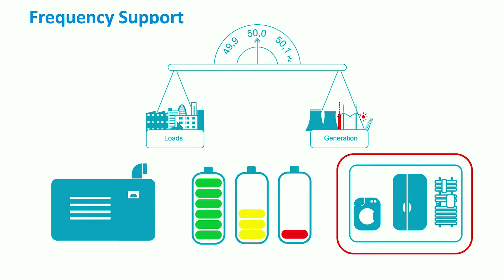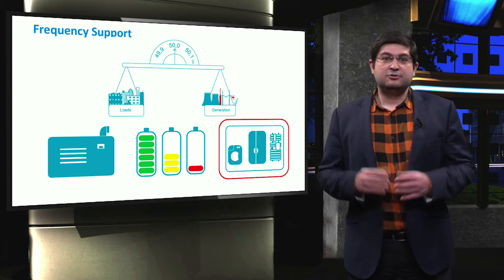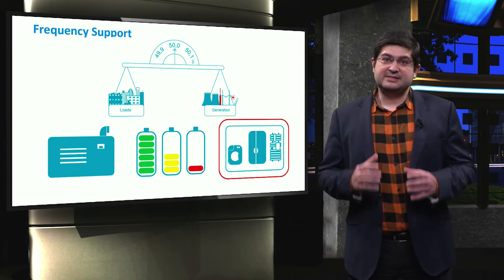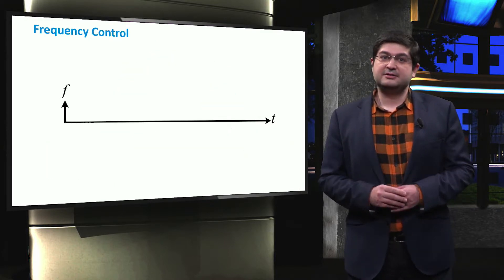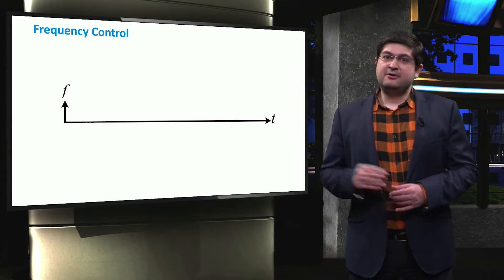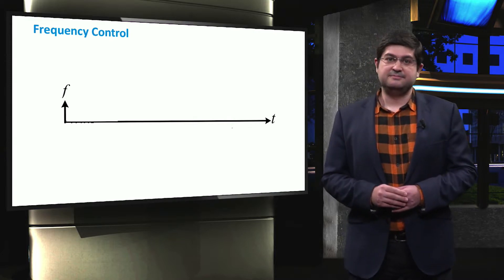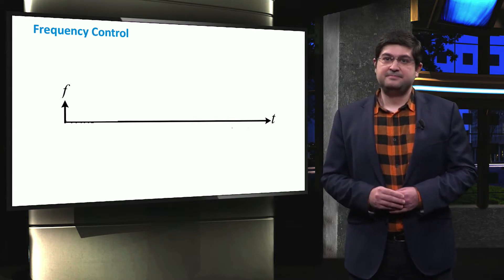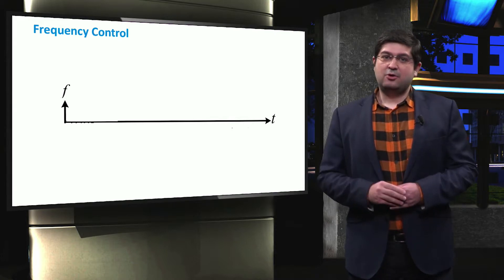The loads can also be controlled and managed in such a way that the frequency is better supported in microgrids. Note that electrical loads are not able to independently maintain the frequency, while diesel engines and batteries are able to keep the frequency stable during the standalone mode. Let's now discuss the frequency control in an islanded microgrid for two types of disturbances: firstly, the case in which generating units are disconnected; and secondly, an islanded microgrid in which loads are disconnected. While the first disturbance will create an under-frequency event, the second one will lead to an over-frequency event.